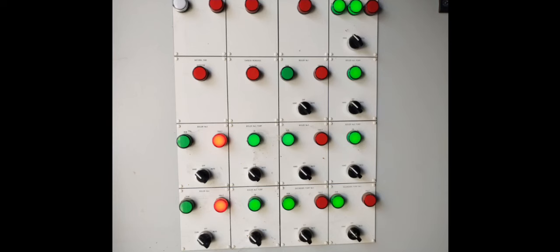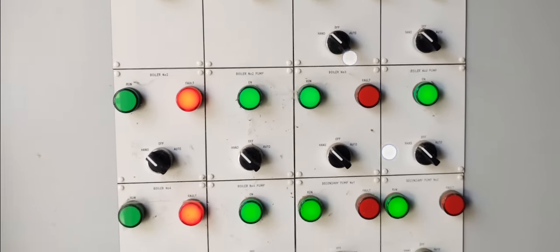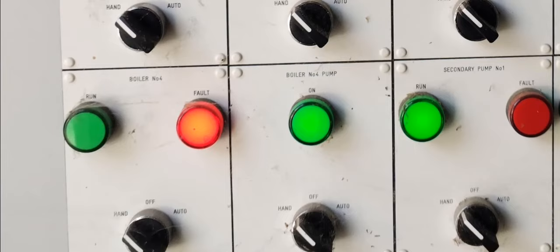And when I arrived at this site when the leak had appeared, at the BMS control panel, I like to take pictures of BMS control panels almost as though you arrive on a crime scene and an accident's taken place. You want to gather all the evidence before tampering with it. So I take pictures of the BMS control panel instantly and try and gather any information, any alarms on the BMS panel, any alarms on the boilers, and write things down.